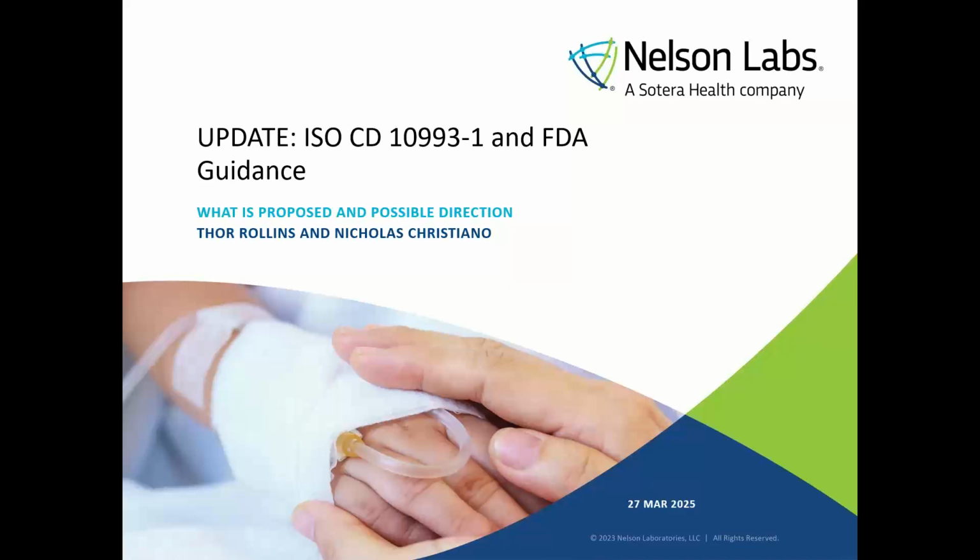Another reason why the standard shifted this way, and a good example, is systemic toxicity. The new charts moving forward will no longer have individually listed acute, systemic, subacute, subchronic, etc. It'll just say systemic toxicity, and it's our job as authors to explain why we're choosing the route we're choosing. So I think the more we explain the why and the how will help us meet the reviewer halfway in the proper understanding and evaluation of these devices.